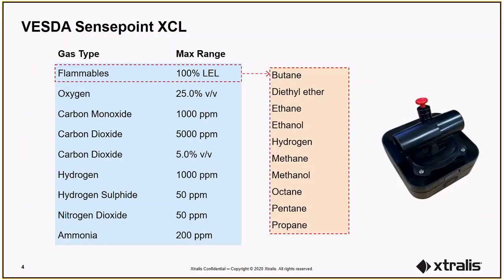Here we see the offering of VESDA Sensepoint XCL detectors for different gas types and the respective maximum monitoring range. The offering covers flammable gases, toxic, oxygen, and carbon dioxide gas threats. In terms of the sensing technologies, the flammable sensors are pellistor, toxic and oxygen are electrochemical, and carbon dioxide is infrared. For the flammable gas version, the sensor is non-selective and will respond to any gas that can burn. It is factory calibrated to methane, but the user, through software, can adjust the selectivity to a specific flammable gas.